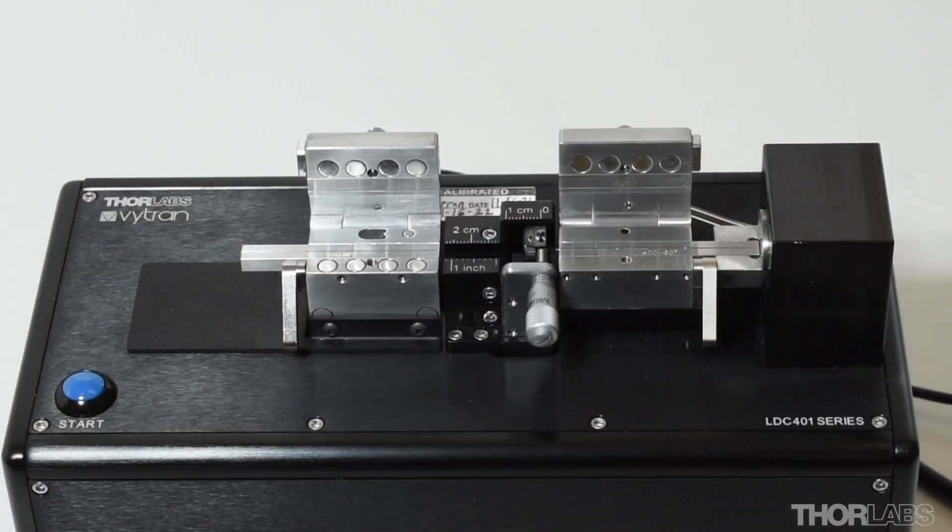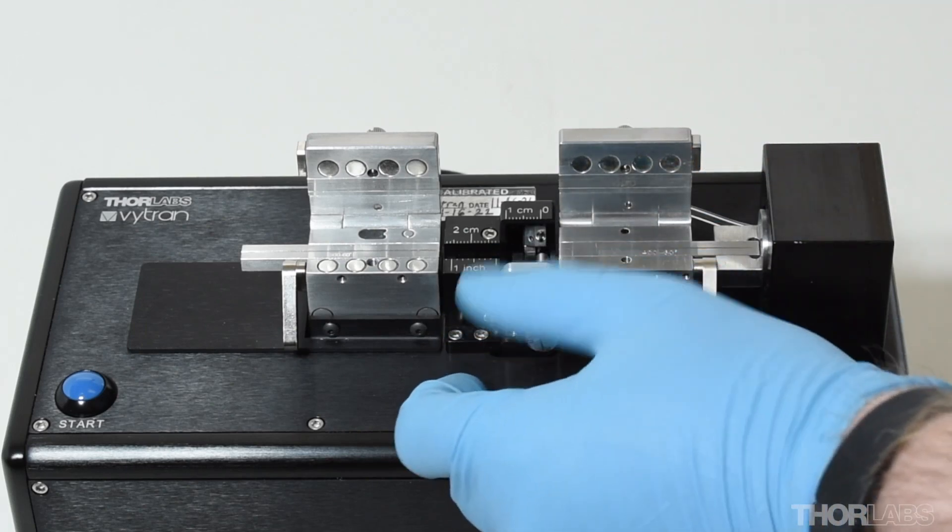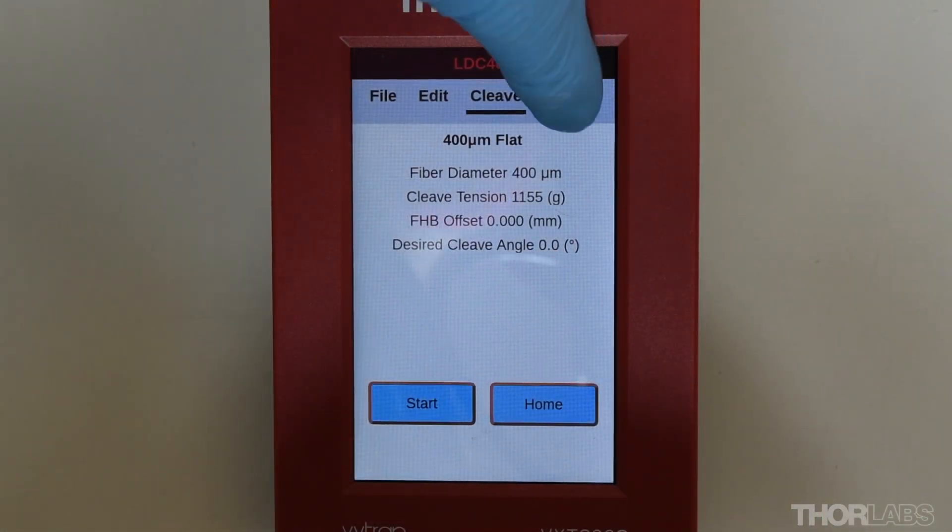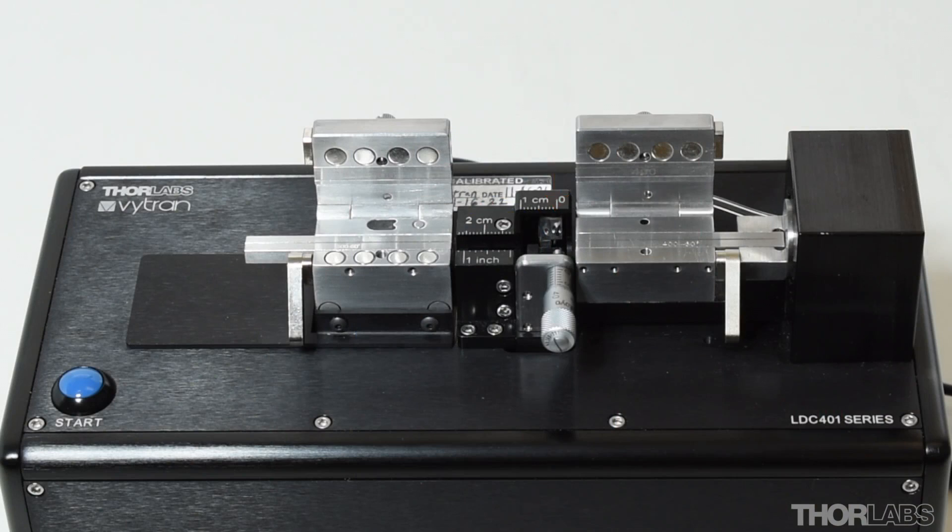Before moving the cleave blade to the service position, ensure there is no fiber debris in the fiber holding block and that the micrometer backstop is fully retracted. Then, use the handset controller to select Tools, Blade Service. This will cause the blade to move forward from its home position to the service position.